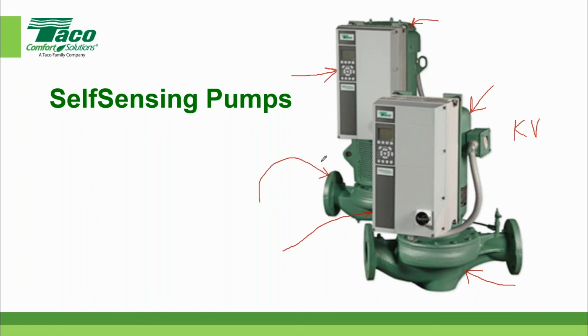But what you can see is that it also has this adapter, and this adapter allows us to have a coupling. This is called a split coupling. The one in the foreground is the close coupled, and the one in the background is the split coupled. But when we think of a self-sensing pump, we think of all three components working together in concert with each other. They don't have to be connected like they are shown here, where the variable frequency drive is physically connected to the pump. This could be remote mounted on the wall somewhere, but all three components work together as a single unit, and we test them in the laboratory as single operating units.